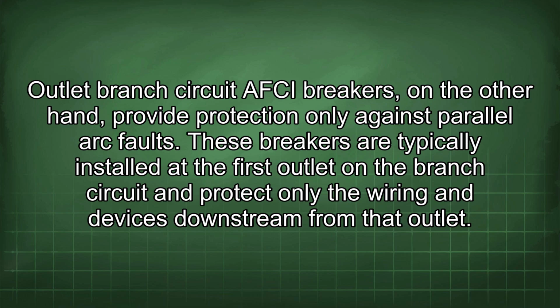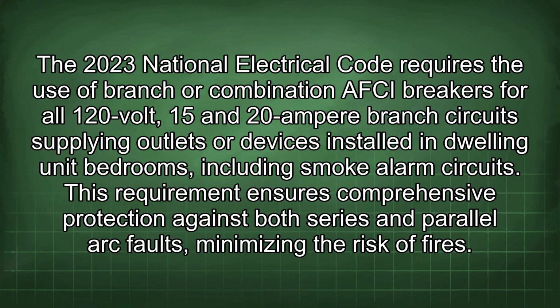downstream from that outlet. The 2023 National Electrical Code requires the use of branch or combination AFCI breakers for all 120 volt, 15 and 20 ampere branch circuits supplying outlets or devices installed in dwelling unit bedrooms, including smoke alarm circuits. This requirement ensures comprehensive protection against both series and parallel arc faults, minimizing the risk of fires.